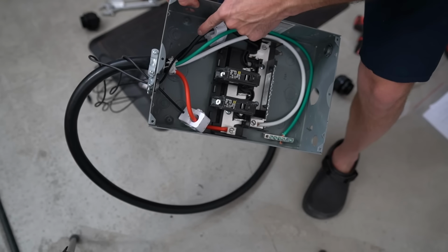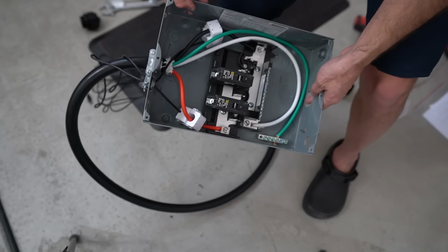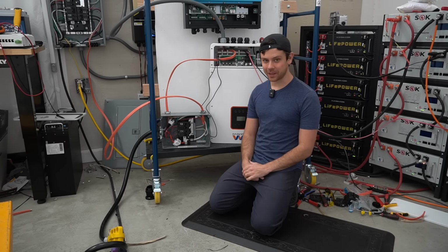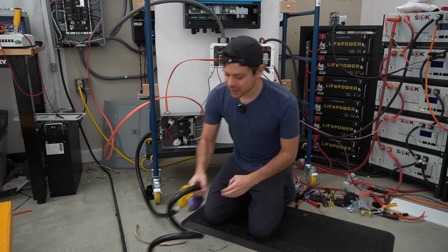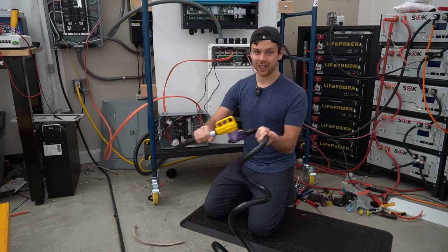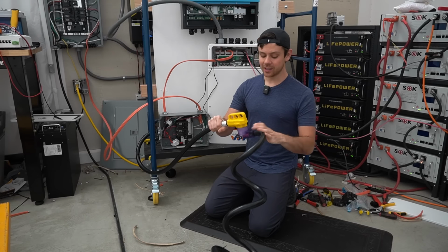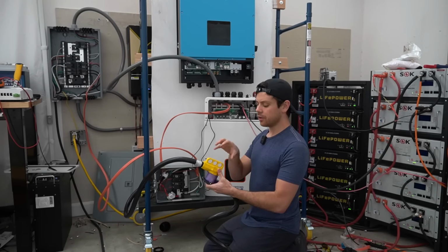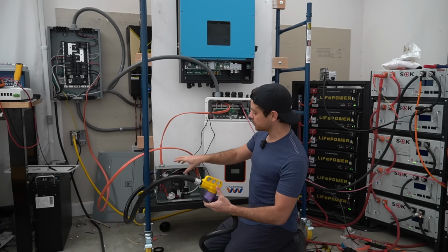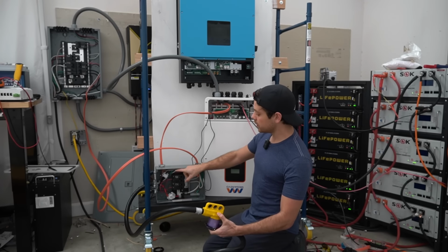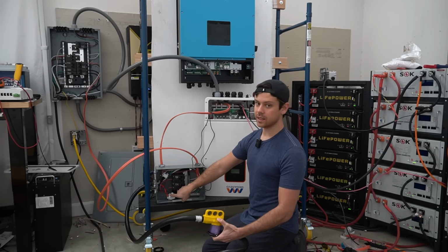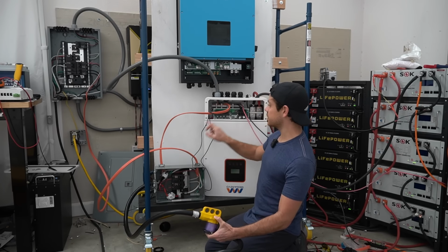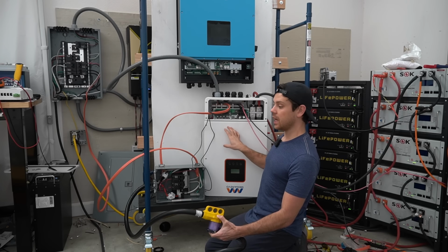So Hot 1 and Hot 2 have their own individual CTs. So this is our test setup and it's very messy. But over here we have a 50-foot, 50-amp NEMA 14-50 supplying the AC input. Now this 240-volt supply goes into the load center, and right when it does, we have the CTs connected. And then this load center is connected to the AC input of the 8K.